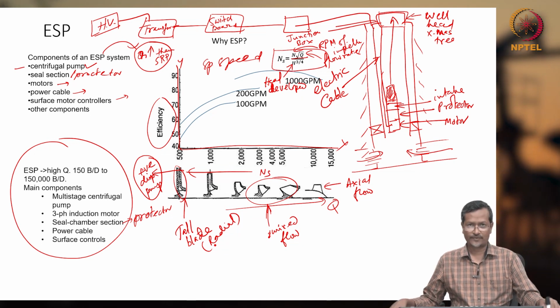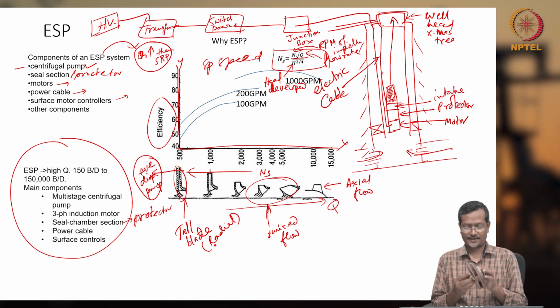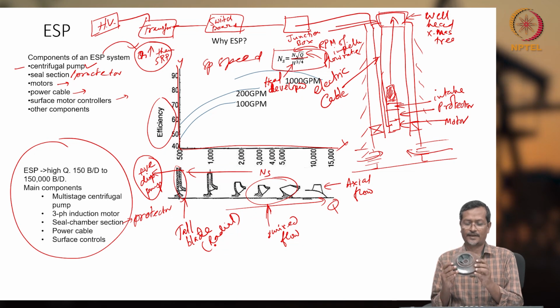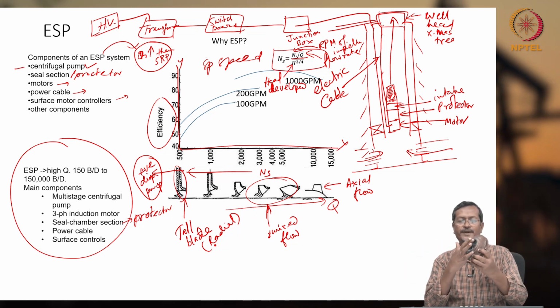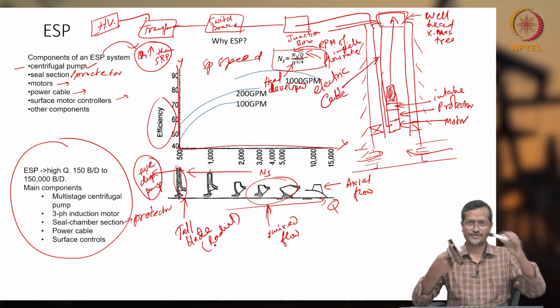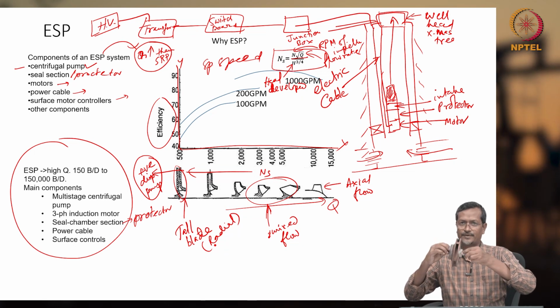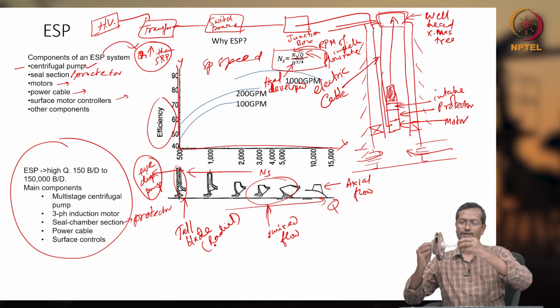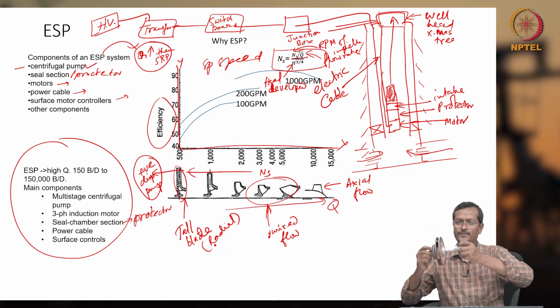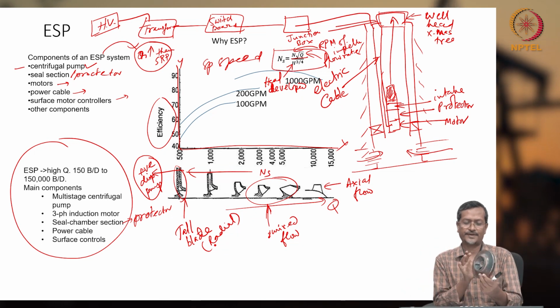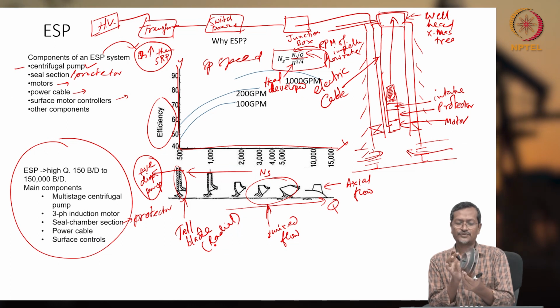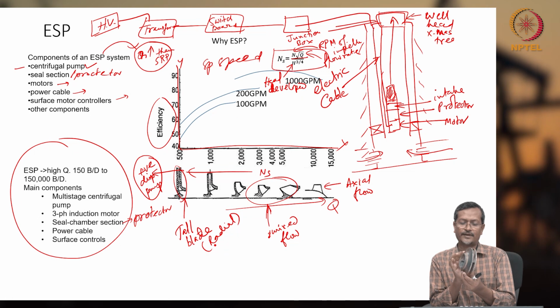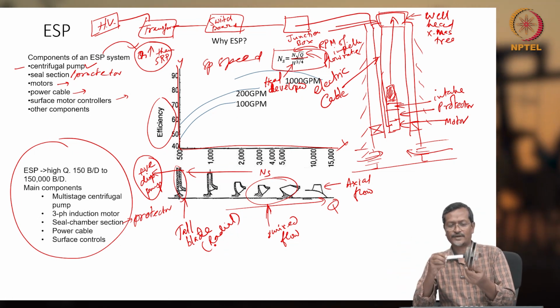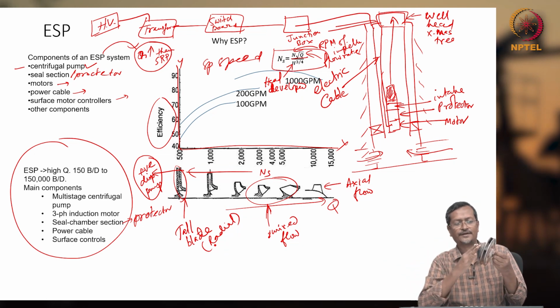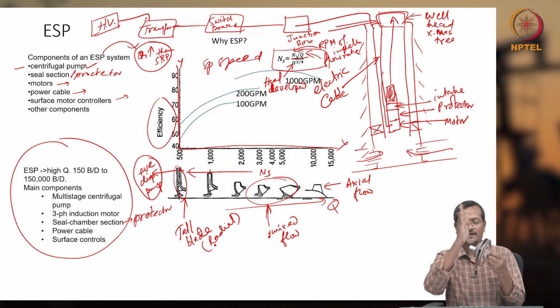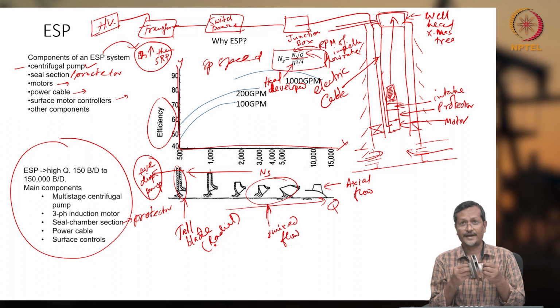Now, what is a radial flow impeller? I have brought my impeller system. This is one impeller, you can see. The impeller has a flow path here, fluid will be entering and it will be exiting. There will be a shaft hole, this is my shaft, and the shaft will be giving rotation to the impeller. When the shaft is connected to your motor and the motor is rotating, your impeller will also be rotating. The impeller is very thin actually, it is a radial flow impeller. Fluid will be entering axially, parallel to the axis, then it will take a turn inside the impeller blade and go vertical, so it will be turning 90 degrees. That is why it is called radial flow, radially turning.